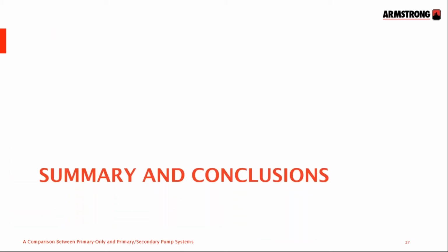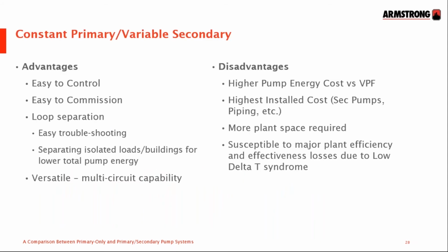So to summarize where we've taken our discussion and draw some conclusions. Constant primary, variable secondary: primarily it's easy to establish, set up, control, and commission. The loops are separate, so it's easy to separate off a loop to do any troubleshooting, and you can also configure the system so that you can tailor the pumping systems and the circuits to suit special applications, loads with a much higher pumping head pressure or a different loading capability, knowing that the flexibility will allow the whole system to operate successfully.